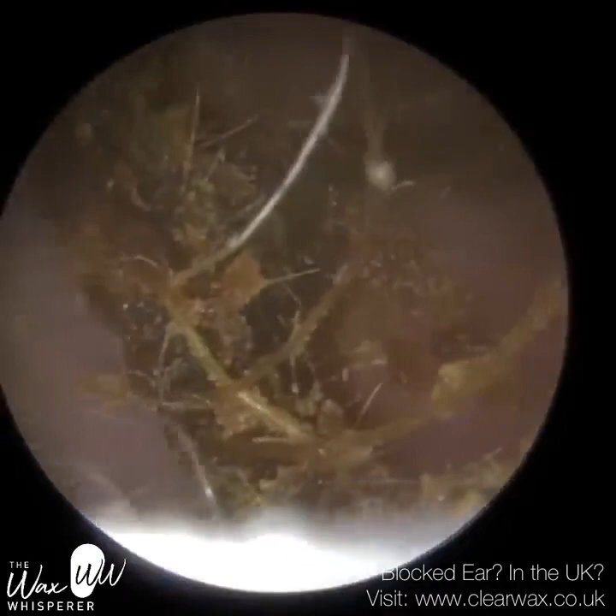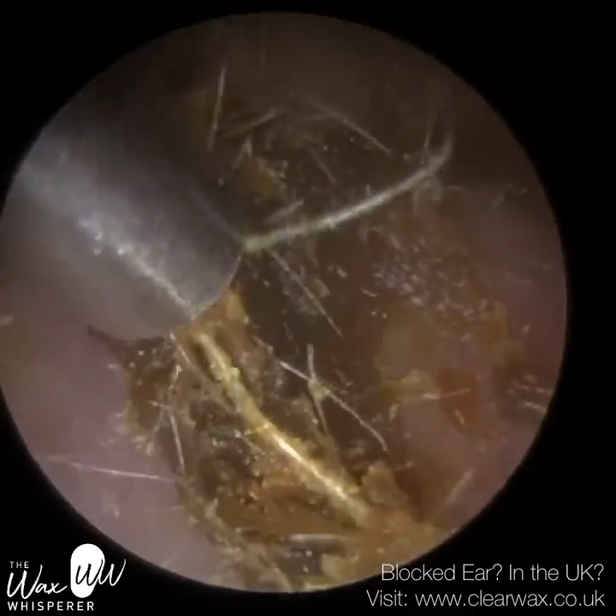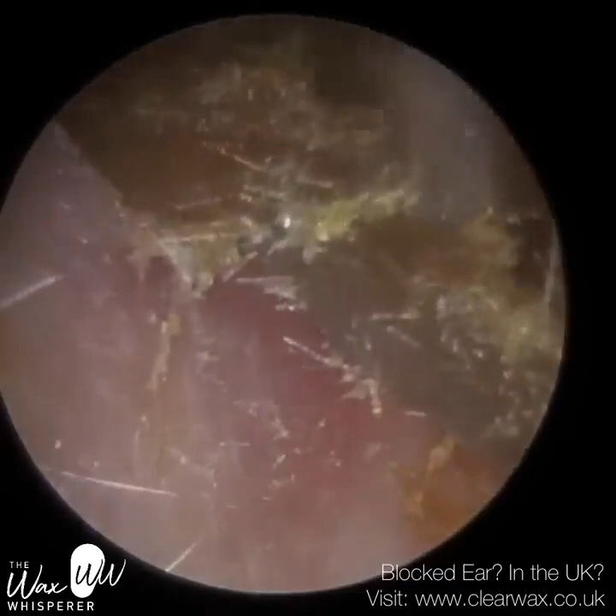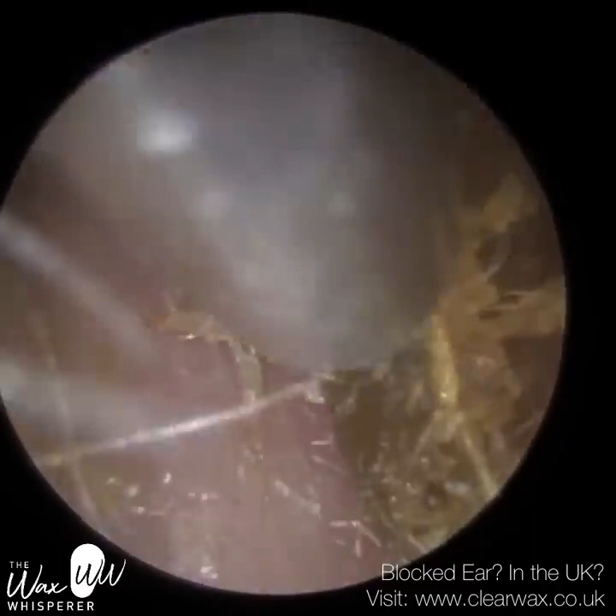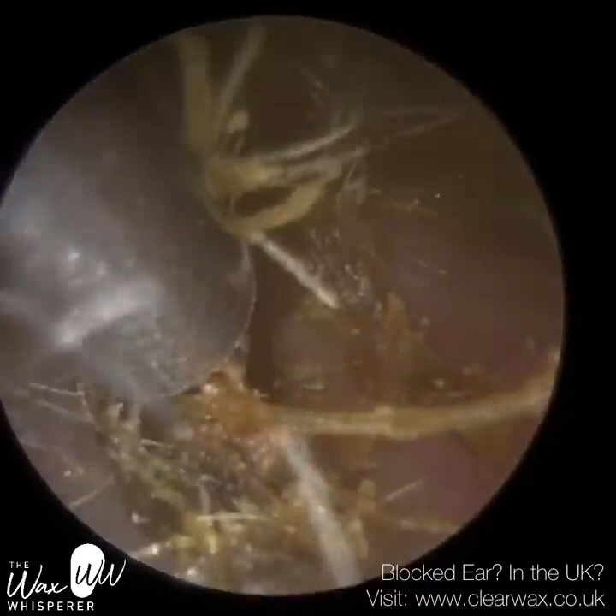So with a fine end, because it's less suction power, you're less likely to get clarinetting. However, I can tell there that I've taken the fine end off just because I haven't got enough suction power. So I've reverted back to the standard full-size Zollner suction probe. The internal diameter of a Zollner suction probe is around 1.7 millimeters. The complete diameter is 2.1 millimeters.